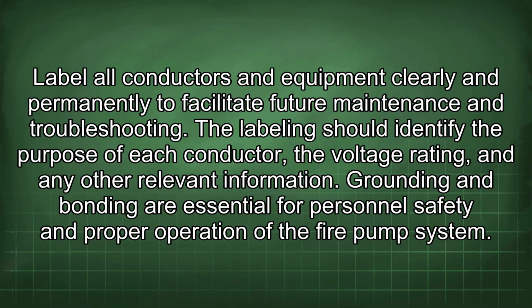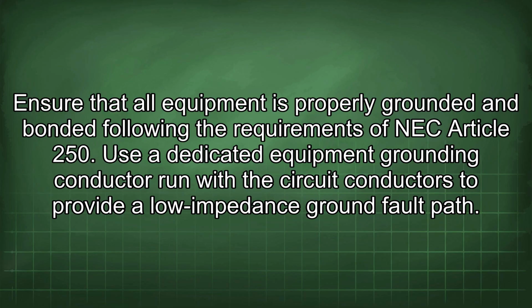Grounding and bonding are essential for personnel safety and proper operation of the fire pump system. Ensure that all equipment is properly grounded and bonded following the requirements of NEC Article 250. Use a dedicated equipment grounding conductor run with the circuit conductors to provide a low impedance ground fault path.